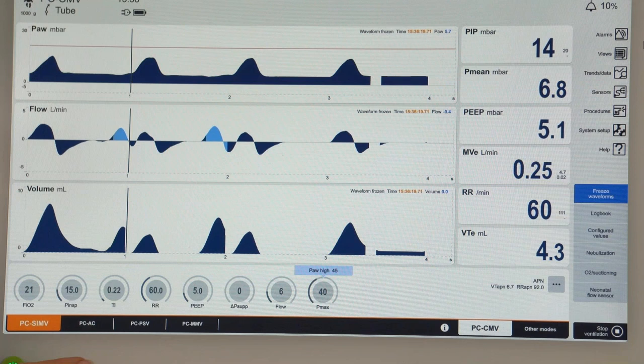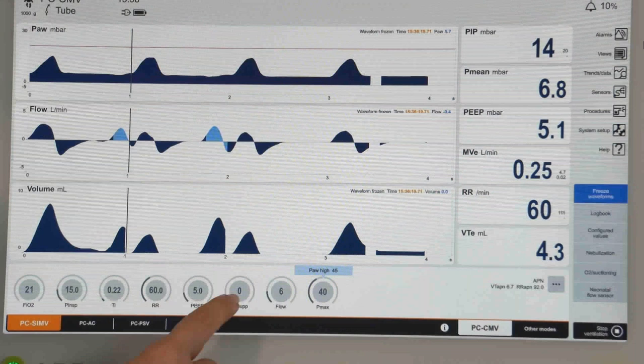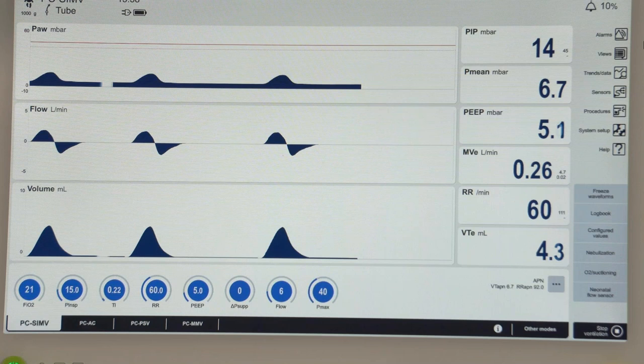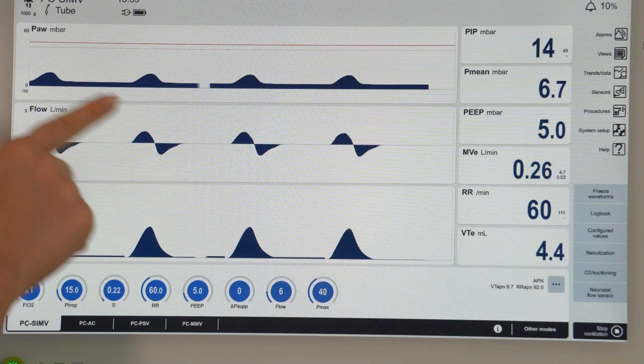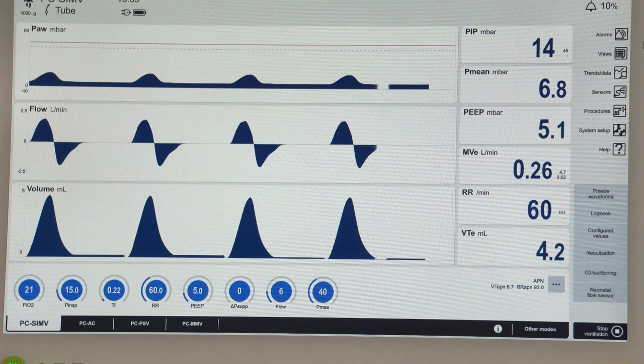If we look at the PC-SIMV mode, we see the same parameters — inspiratory pressure, respiratory rate, inspiratory time and PEEP. When we activate PC-SIMV, the curves look the same, but the key advantage is synchronisation — there is now a trigger window in which the patient can trigger a breath. We can see there is no more breath stacking. The patient starts inhalation, and the moment the trigger criteria is met, the ventilator starts the mechanical breath. We can see the lung symbol indicating that the patient triggered the breath.